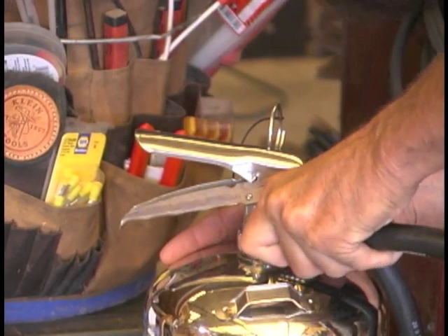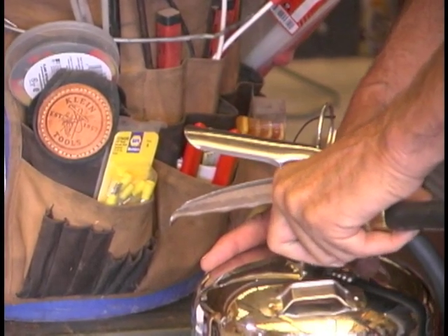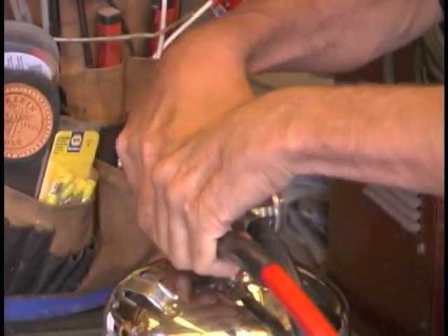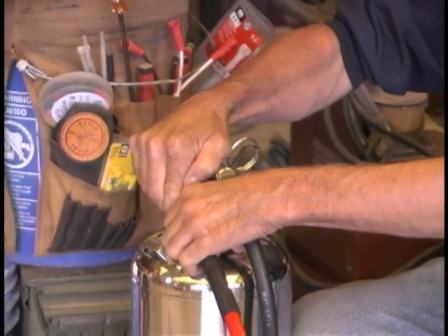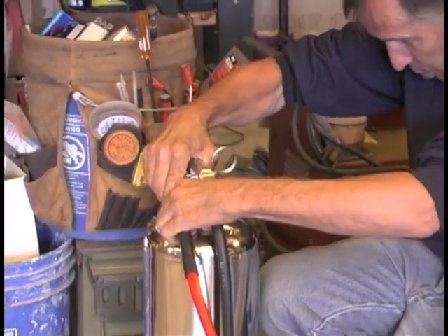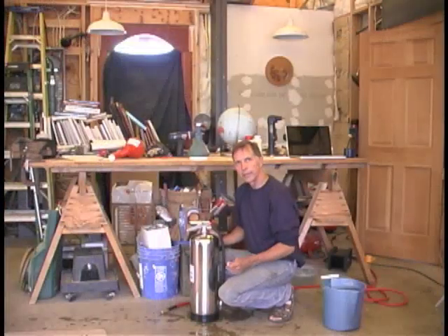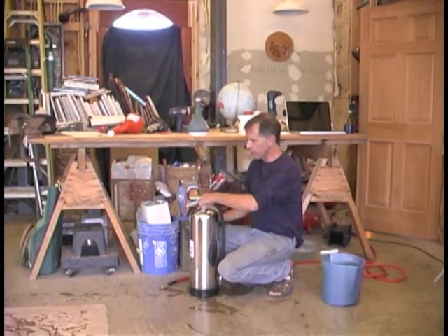You know it's working because you can hear the air going in and churning up the water that's in there. We're coming up to the green. You've got to make sure the compressor you're using can build up more than 100 pounds of pressure, because that's what this unit requires — right in the middle. When you've got the air pressure where you want it, put that little cap back on to keep it from leaking.